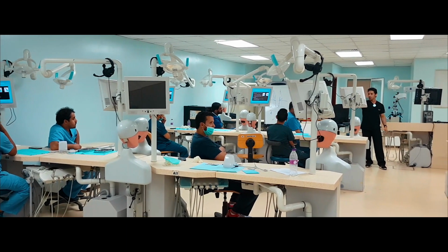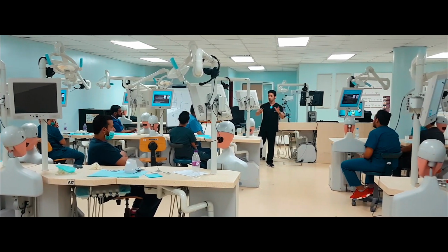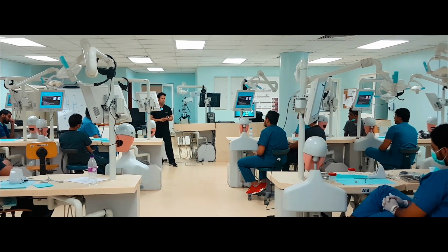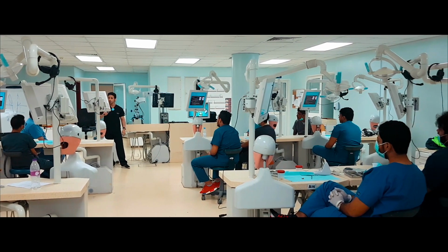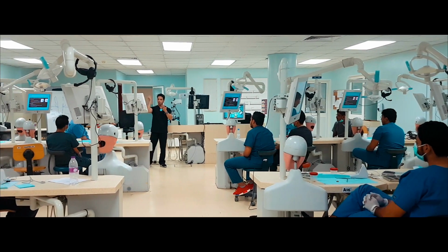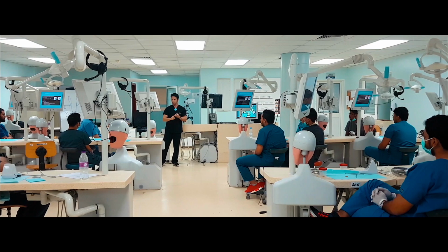All the green stuff, 1, 2, 3 is nonsense, okay? I think they put it for fun. It looks beautiful. There are 2 main things you have to do when you use an apex locator. Number 1, make sure the battery is full. Number 2, you touch the hook with the tip. If it goes to the red, that means it's working.